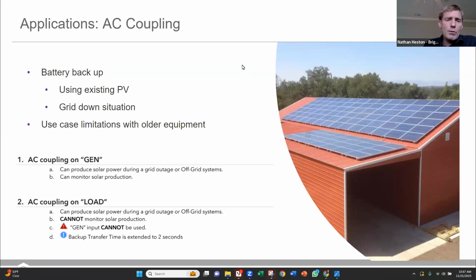It's important to keep in mind how you AC couple, as it can influence what you're trying to do. You might want to AC couple through the loads port of an inverter. This is pulled out of a Sol-Ark manual. If you also want to integrate other equipment, for instance, and you want to use the gen port, you would need a transfer switch on your generator in order to be able to use both AC coupling and the generator port. That's the same on our inverter. If you want to AC couple in solar, you can absolutely do that. We can take up to 40 amps on the Briggs & Stratton inverter. But again, you would need a transfer switch if you want to integrate a generator.